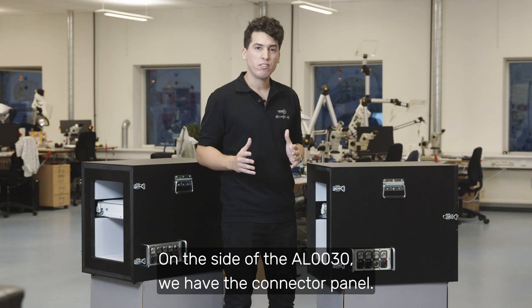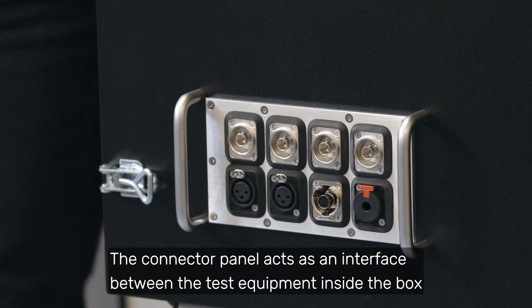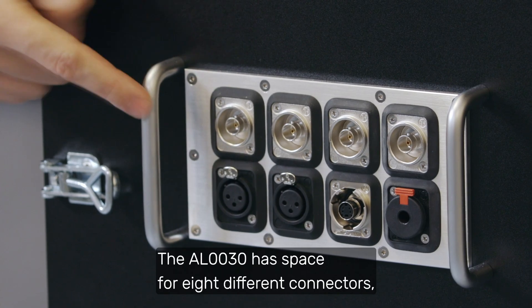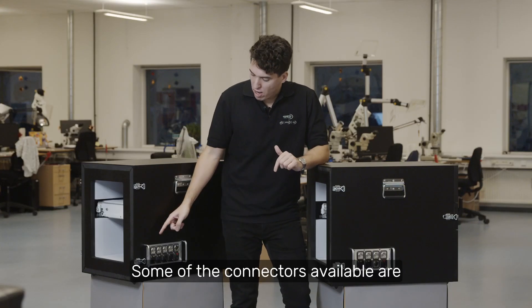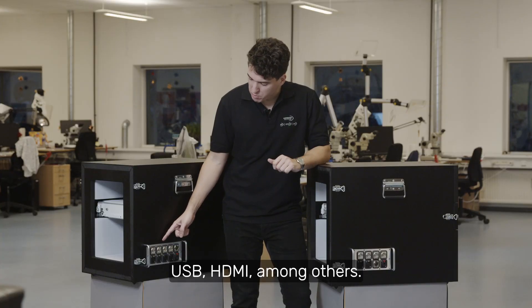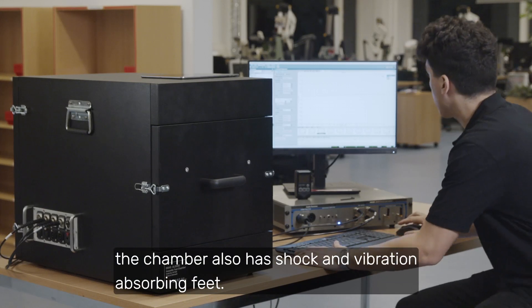On the side of the AL0030, we have the connector panel. This can be customized with a range of connectors. The connector panel acts as an interface between the test equipment inside the box and the data acquisition system or analyzer on the outside. The AL0030 has space for eight different connectors, while the AL0030S2 has space for ten. Some of the connectors available are BNC, XLR, RCA, Speakon, quarter-inch jack, Ethernet, USB, HDMI, among others. If you would like to use a custom connector, we can leave a blank plate so you can add your connector of choice later. The chamber also has shock and vibration-absorbing feet to prevent vibration from external sources from influencing the measurements.